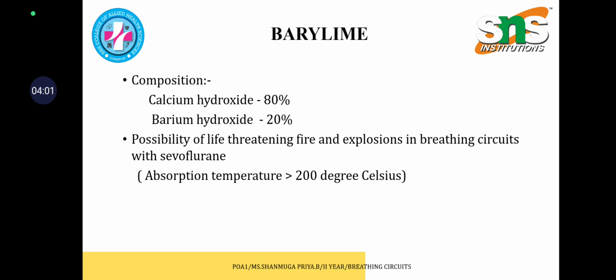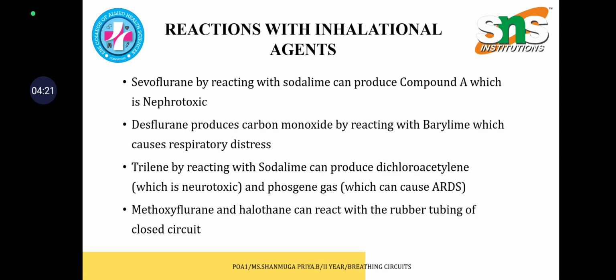For Barylime, which is another carbon dioxide absorbent, the composition is calcium hydroxide 80%, barium hydroxide 20%, and there is the possibility of life-threatening fire and explosions in breathing circuits with sevoflurane, because the absorption temperature is more than 200 degrees Celsius. Reactions with inhalational agents.